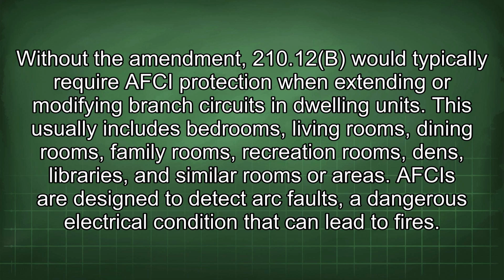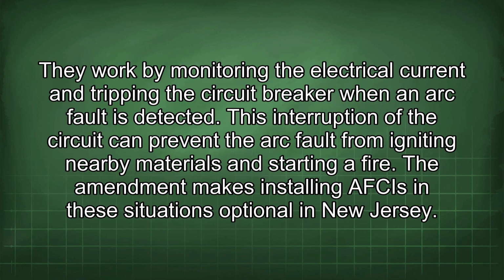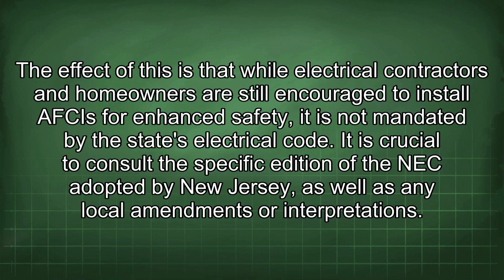AFCIs are designed to detect arc faults, a dangerous electrical condition that can lead to fires. They work by monitoring the electrical current and tripping the circuit breaker when an arc fault is detected. This interruption of the circuit can prevent the arc fault from igniting nearby materials and starting a fire. The amendment makes installing AFCIs in these situations optional in New Jersey. The effect of this is that while electrical contractors and homeowners are still encouraged to install AFCIs for enhanced safety, it is not mandated by the state's electrical code.